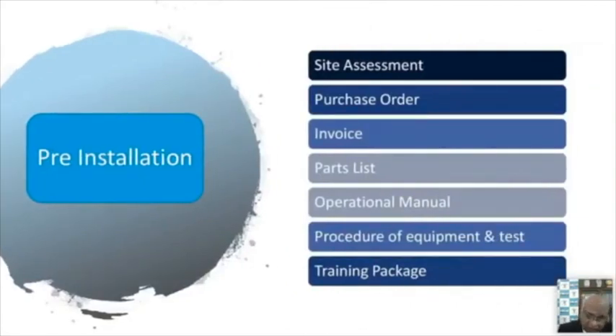IQ means installation qualification, OQ means operation qualification, PQ means performance qualification. But before installation, we have to see certain things. We have to maintain certain records. Site assessment, if it is big machines, site assessment by manufacturer or supplier, then purchase order, copy of invoice, list of parts provided with the machine, operational manual, procedure for that equipment, and also develop SOP for tests, and also you shall have training package with the machine.